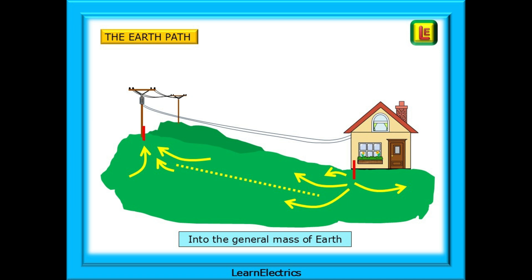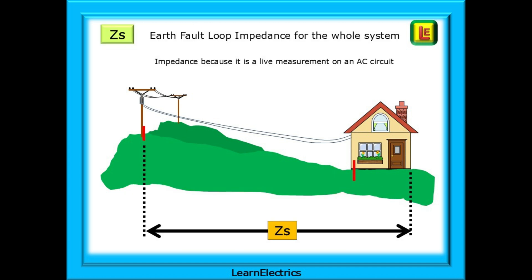The earth path, during a fault, relies on the general mass of earth. Electrons will be displaced into the soil in the vicinity of the house earth rod, and electrons will be taken up by the earth rod at the overhead pole. ZS is the earth fault loop impedance for the whole system. If there is an earth fault, it is a path from the point of fault in the dwelling, through the internal earth or CPC, out of the property, and through the earth to the supply transformer, and then back along the line conductor to the point of fault.